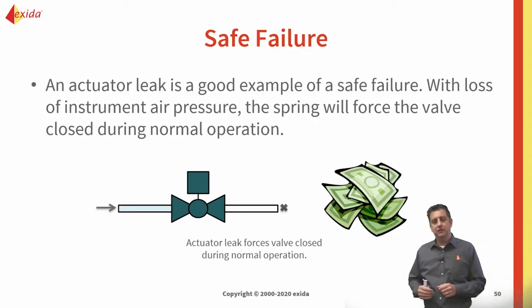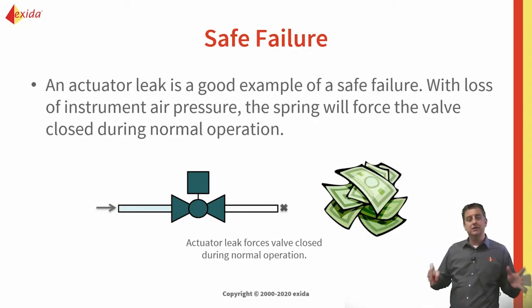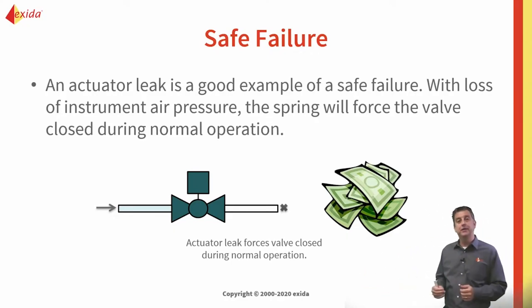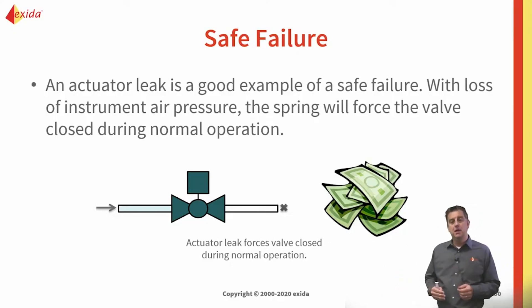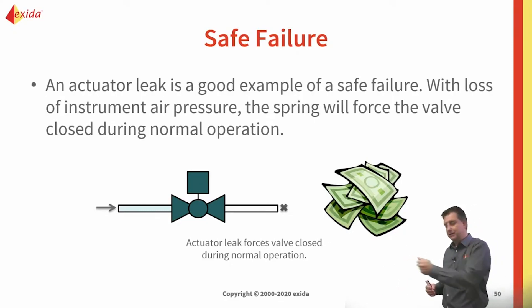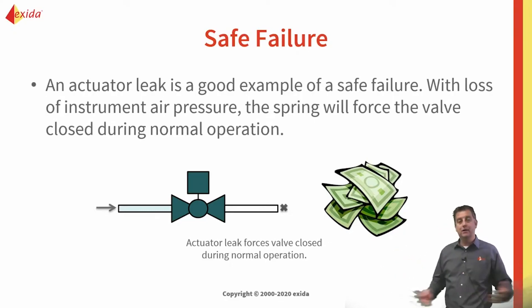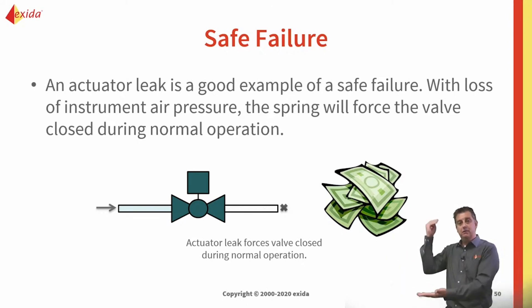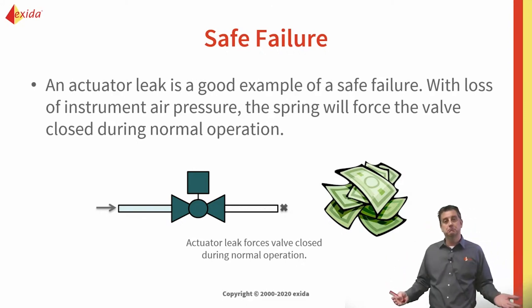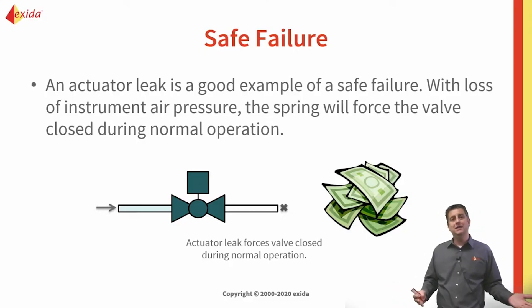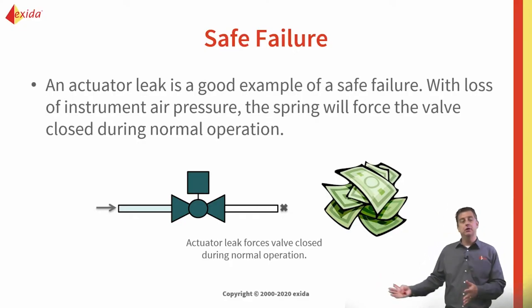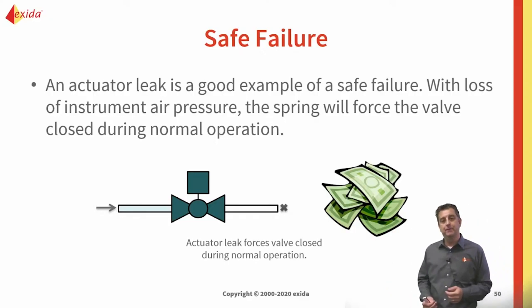What are safe failures? Safe failures are failures that bring the process to the safe state when there is no dangerous or hazardous scenario. An example would be: I have flow going, I just want to keep operating and producing, and for whatever reason that valve suddenly closes. We don't like these failures because they shut down our process, meaning we're not producing and we lose money.